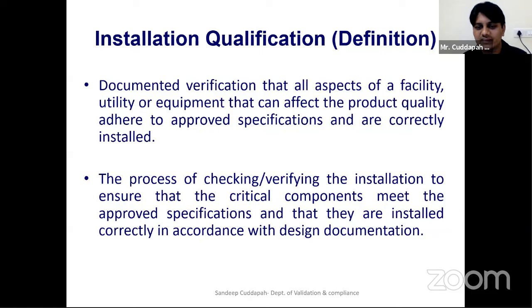Suppose you take one simple equipment, an autoclave. During installation qualification of the autoclave, you will verify how many compressors are connected to it, what kind of material has been used in manufacturing, their measurements, and what the chamber size is. The accurate measurements and accurate specifications of each part will be mentioned in the installation qualification.